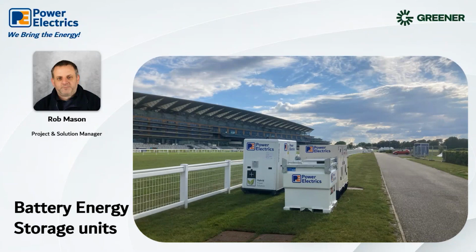Phrases such as wet stacking in the industry or low loading can be solved with the use of the batteries as well. So a 300 kVA generator running at 30 kVA, but it's there to deal with the load spikes. The battery is used to cover this. As sustainability comes to the forefront, energy storage and efficient use is becoming more important, both from a cost and emissions point of view.